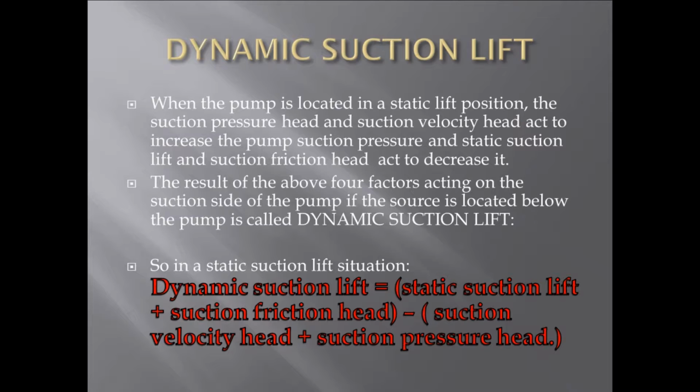The result of the above four factors acting on the suction side of the pump, if the source is located below the pump, is called dynamic suction lift. So in a static suction lift situation, dynamic suction lift equals static suction lift plus suction friction head minus suction velocity head plus suction pressure head.